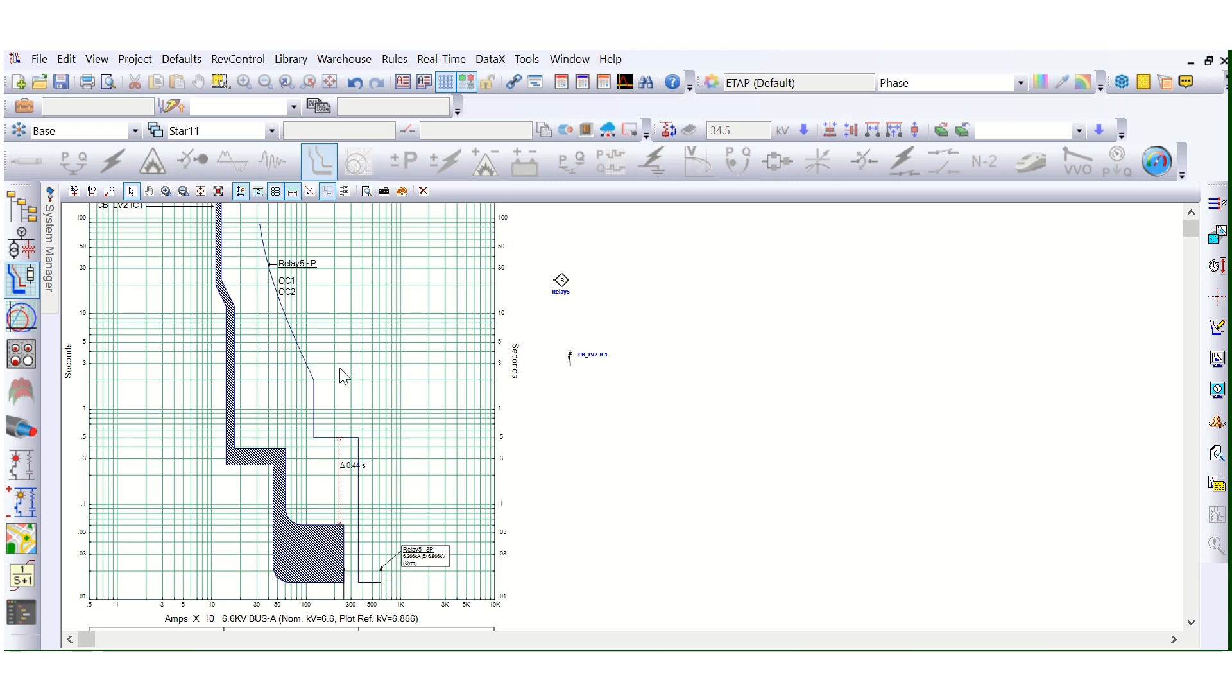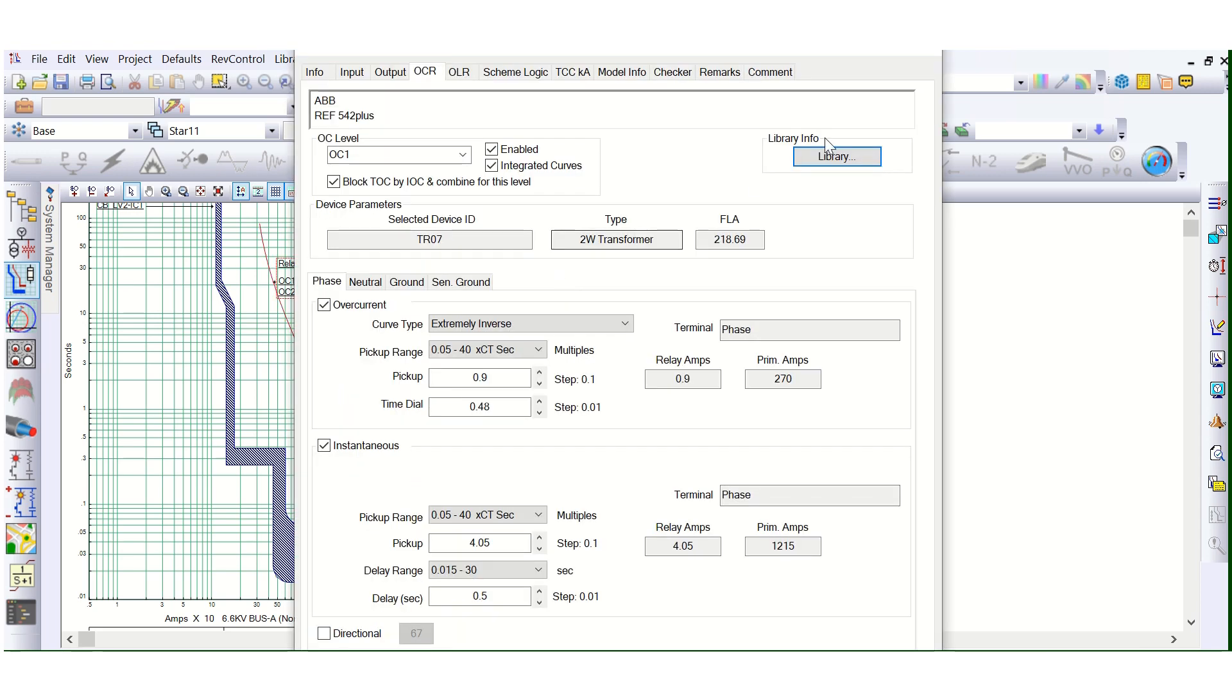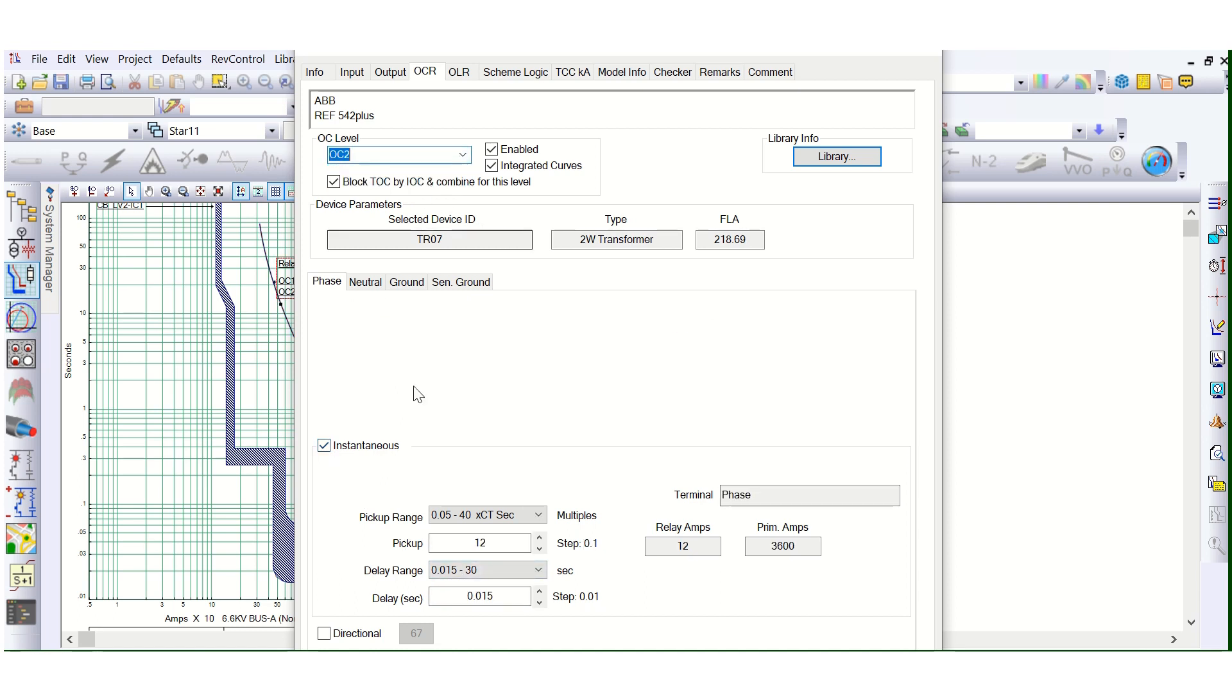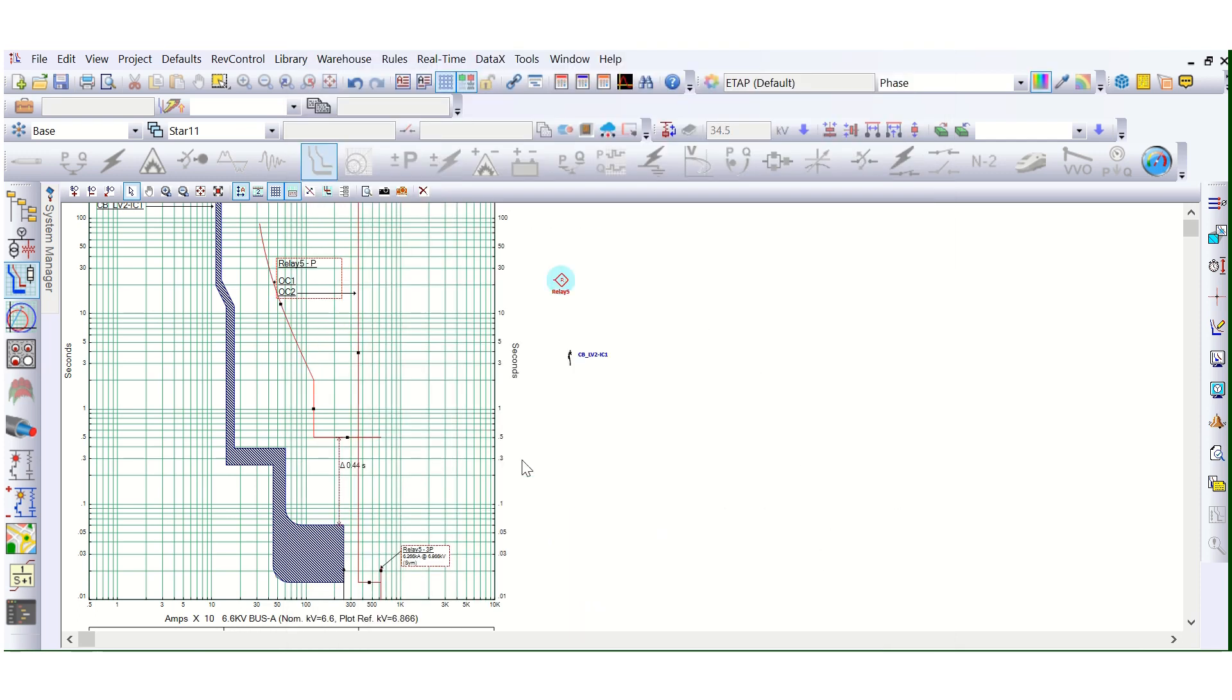To coordinate for better coordination with downstream or upstream network, you can use different stages by the use of these settings. See, this is under OC1, this is 51, this is 50, but short time. And under OC2, only this instantaneous. This is truly instantaneous, that means there is no intentional time delay. So this is the main thing for the different stages for the relay protection coordination purpose.